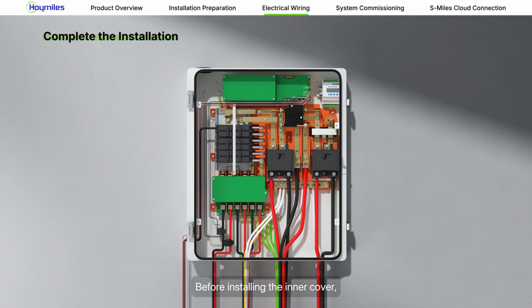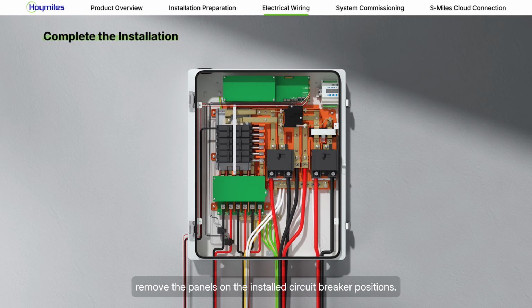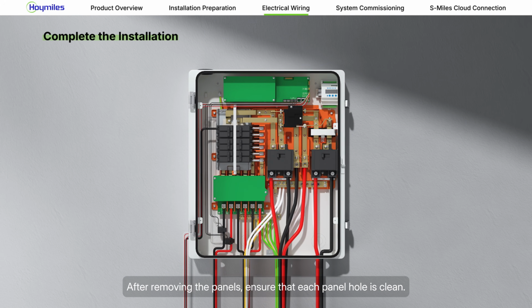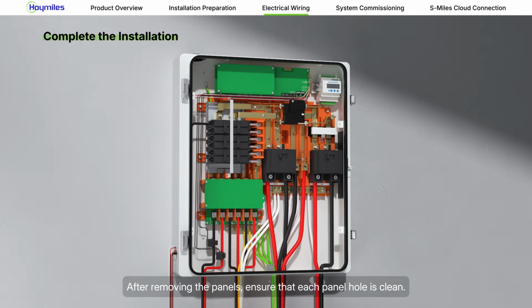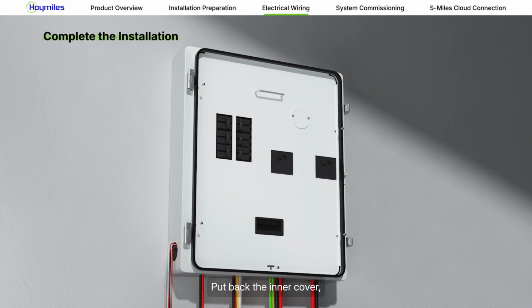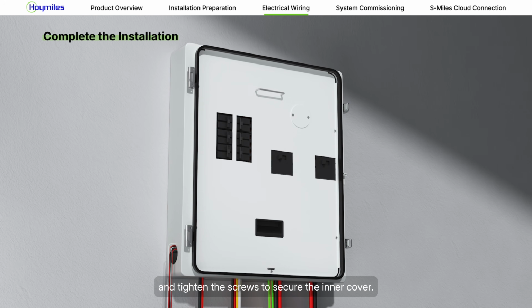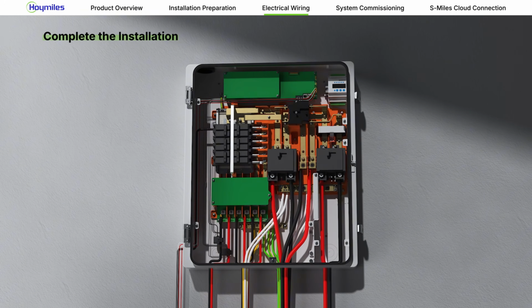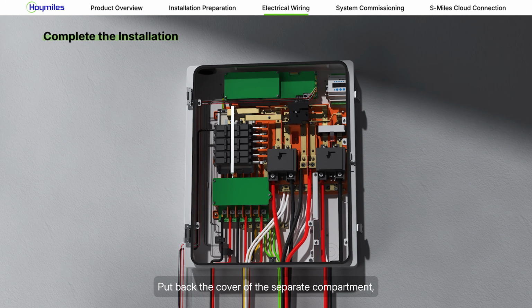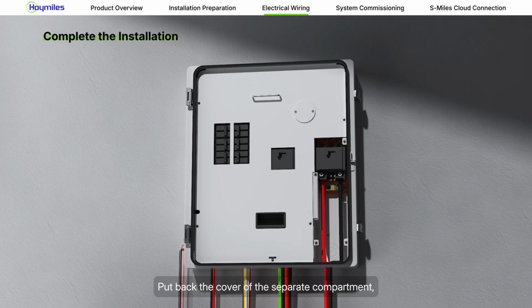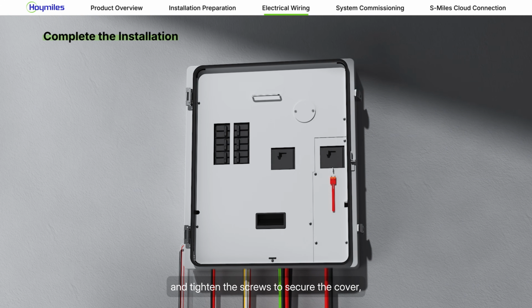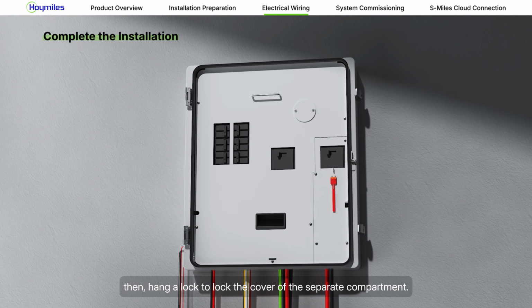Before installing the inner cover, remove the panels on the installed circuit breaker positions. After removing the panels, ensure that each panel hole is clean. Put back the inner cover and tighten the screws to secure the inner cover. For CA-G1, put back the cover of the separate compartment and tighten the screws to secure the cover, then hang a lock to lock the cover of the separate compartment.